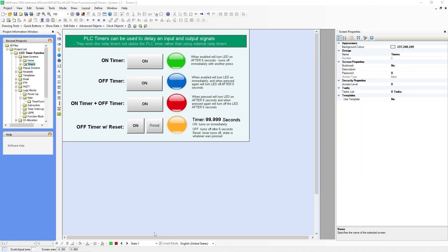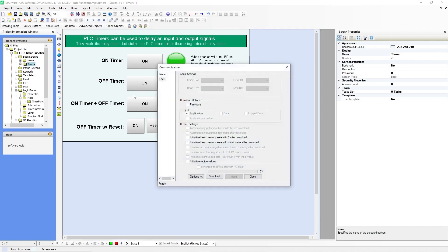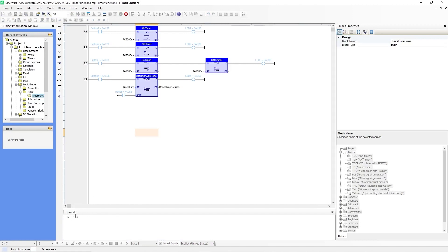Now you are ready to download and go online. Go up to mode, go online with download. If you are downloading for the first time, make sure you have firmware checked off. In this case, I've already downloaded once, so I'm just going to have application checked off. Hit download. It may take a few seconds for the HMC device to load the application. Once it does, it will say run in the compile window and you know it's running properly.